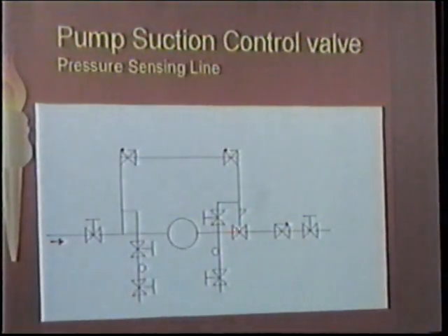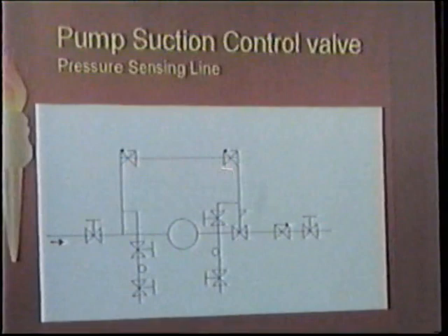Here's the piping schematic for the sensing line. Here's the pump. Here's your city water supply, main shut-off. The sensing line looks just like a controller sensing line: 1/2-inch pipe, same orifices, everything, because that'll allow us to test it. It's not a code-required sensing line arrangement, but it is the only way that I know of that you'll be able to test that valve down the road to make sure it works without starving the pump. Because in most cases, the pump will have to be running and water will have to be flowing in order to test that valve. So then you come back here, it goes to the pilot valve line, and then you have your same valve, gauge, valve setup. And you'll notice that these checks are in backwards.